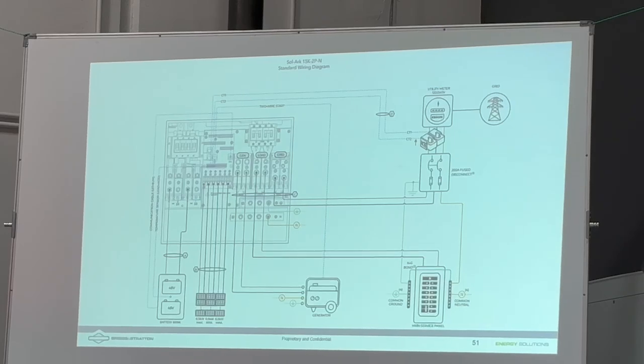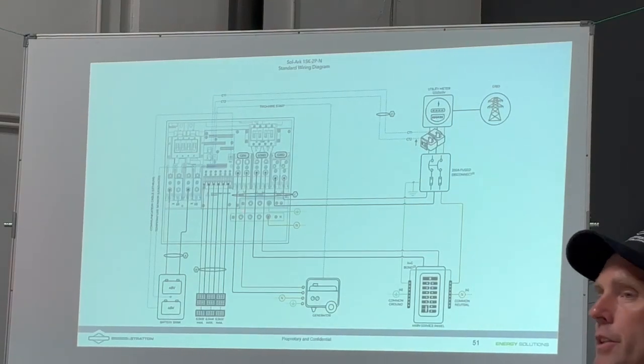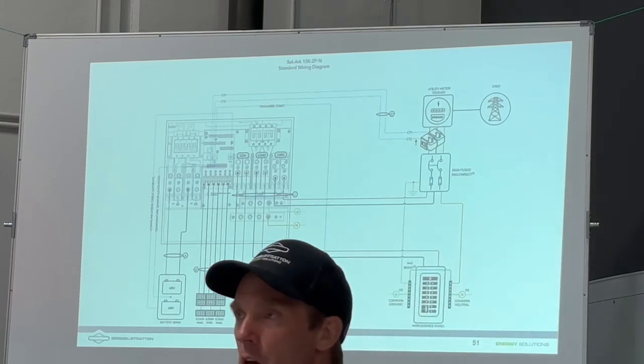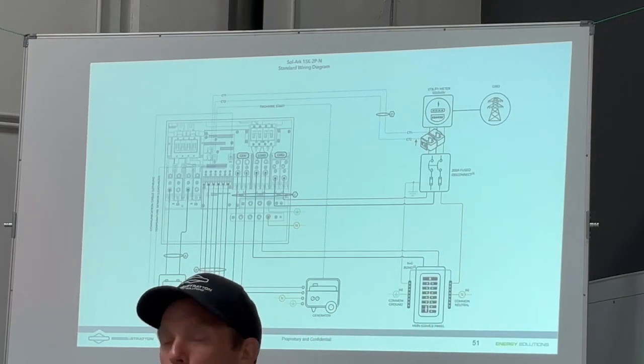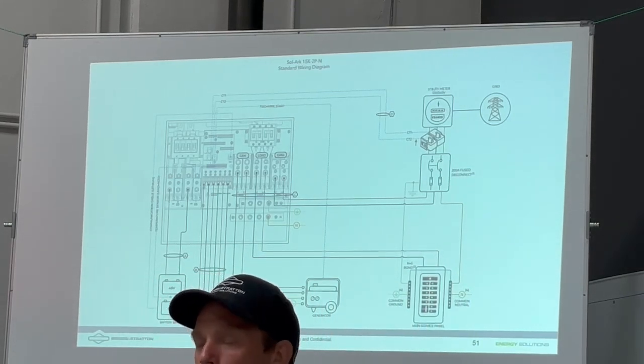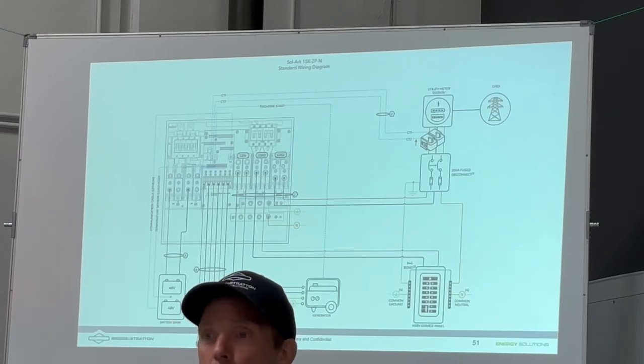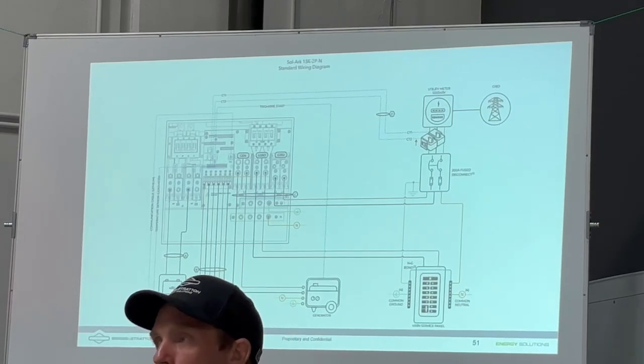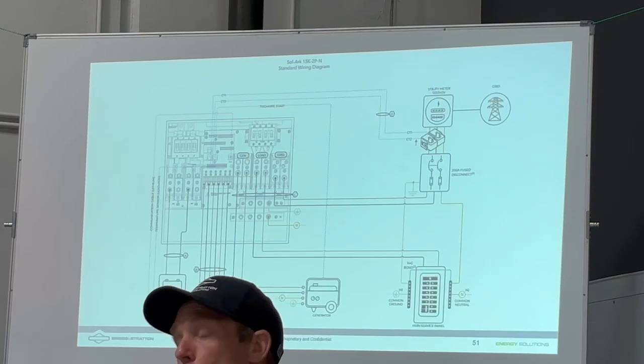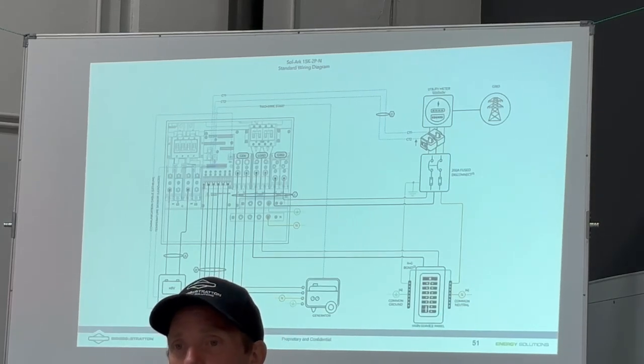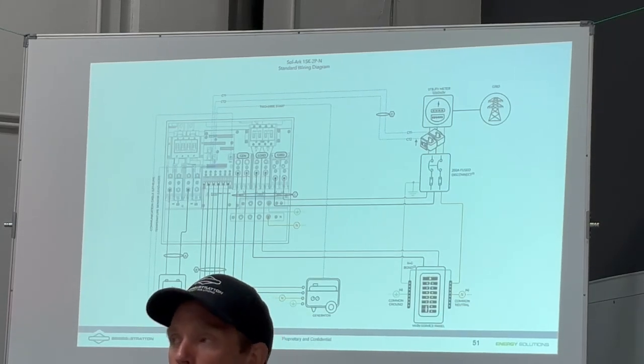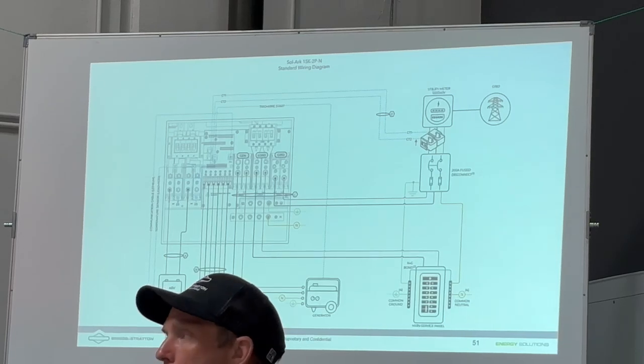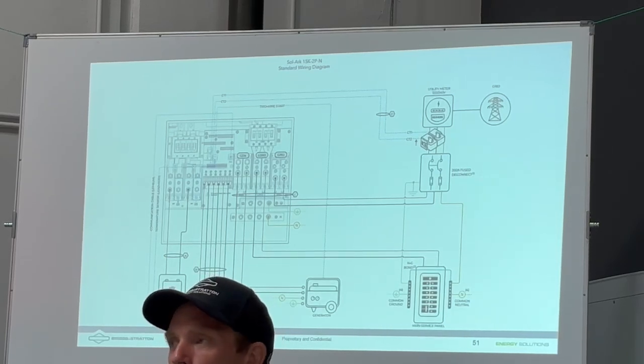But there are kind of two options to bring a generator into a Sol-Ark 15K. One is to just bring it in through the gen port. Another is you've got a 15K on a home that already has a big generator, like a Briggs 26K, already backing up the whole home. It's on a transfer switch. It's got an automatic transfer switch on there. You could take that automatic transfer switch off the wall and wire it in through the gen port on the Sol-Ark 15K.